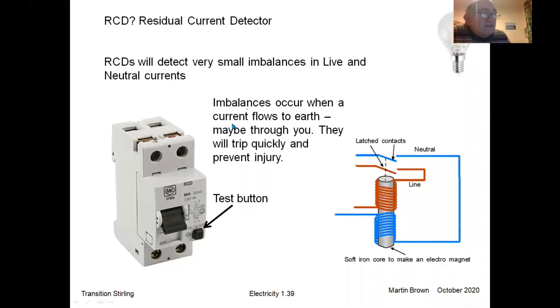It means that if there's a current flow to earth, it could be going through you, not through the metal of a washing machine. Suppose you've got your hand on the washing machine and you somehow touched a live contact, that current flows through you. Fortunately, the residual current detector will detect that and it will open the trip. Above all, do not try this at home, because the RCD might be faulty for some reason. It's not a good way to test these things. Use the test button if you want to try it out.